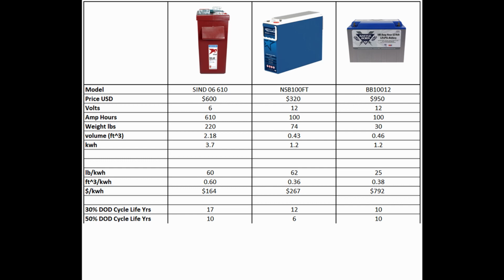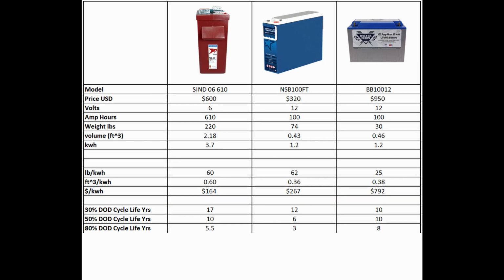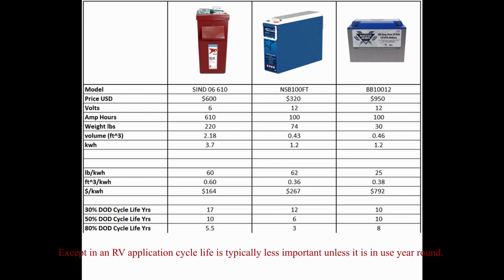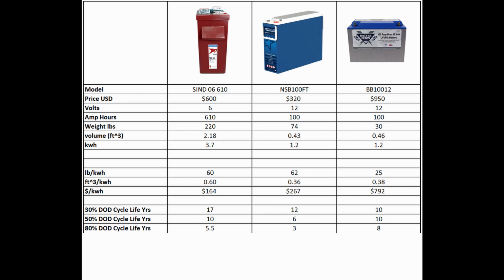At the very extreme, 80% depth of discharge every day, which is entirely impractical for any real-world application, now we see lithium start to look much better. Still, this isn't useful since a system designed to be discharged to 20% state of charge every single day is a poor design, except in special cases, which certainly do exist. RVs, perhaps, where room is very limited. Here we would get 5.5 years out of a flooded battery, 3 out of our AGM, and 8 out of our lithium. Finally, let's look at float life.